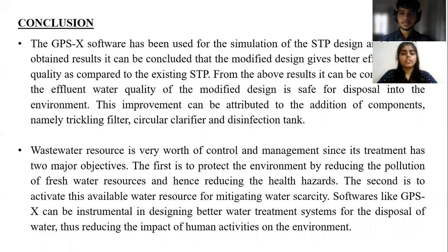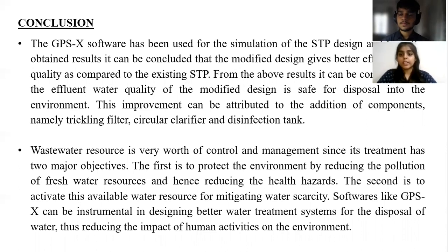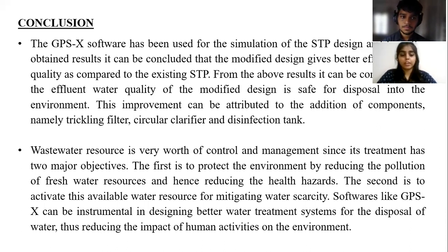The GPSX software has been used for the simulation of the STP design, and from the obtained results it can be concluded that the modified design gives better effluent water quality as compared to the existing STP. It can be further concluded that the water quality of the modified design is safe for disposal into the environment. This improvement can be attributed to the addition of components, namely the trickling filter, circular clarifier, and disinfection tank.